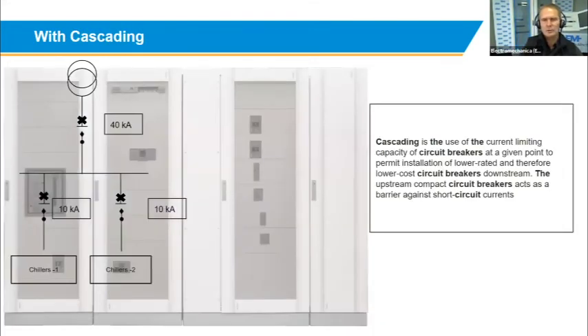Okay, so what is cascading? Cascading is the use of the current limiting capacity of a circuit breaker at a given point to permit installation of lower rated and therefore lower cost circuit breakers downstream. The upstream compact circuit breaker acts as a barrier against short circuit currents.